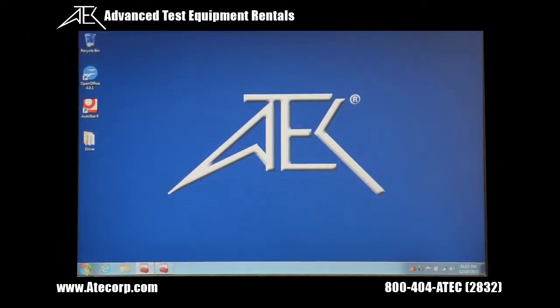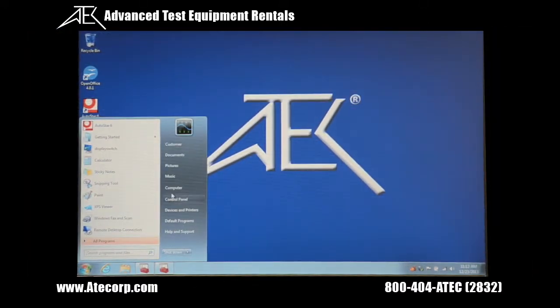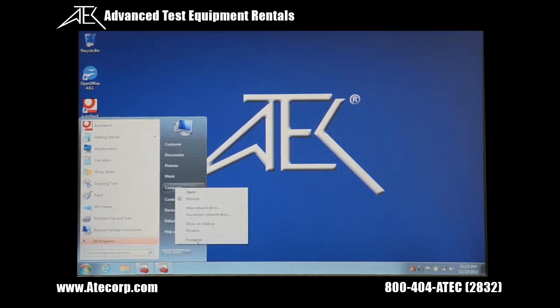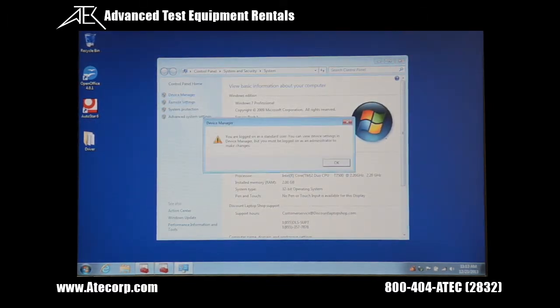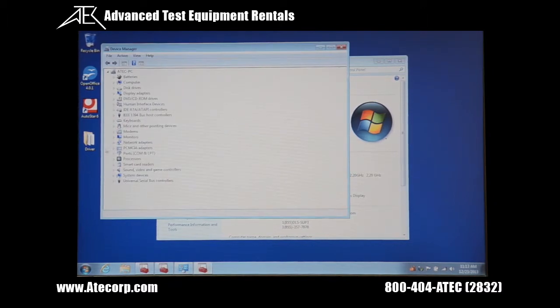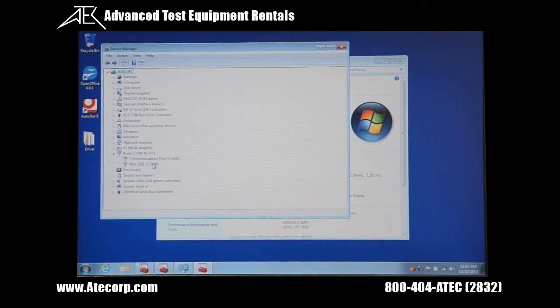The first thing you do is power up the laptop. Once you're powered up, go to Computer, Properties, then go to Device Manager. This error will show because you're not running it as an administrator, so you go OK. Go to Ports and you'll see that the NSG 5500 is COM Port 4. Write that down for future reference because you may need it if you disconnect the computer and re-hook it up and have any problems communicating at a later time.